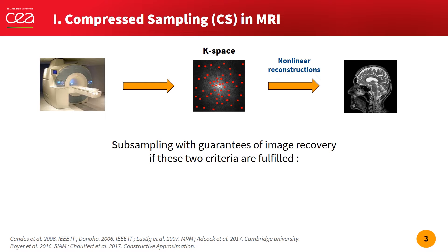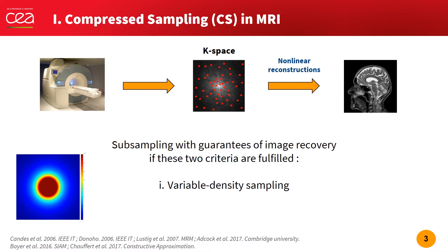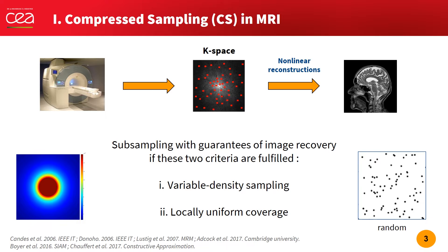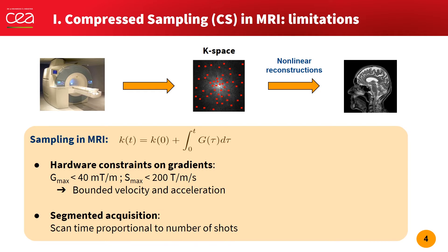It has been shown that the samples should be distributed along a variable density that is concentrated in the low frequencies of the k-space. Another more general principle for optimal sampling is to have a locally uniform coverage, which allows avoiding gaps and clusters of samples that are typical of random sampling. These two criteria are, however, difficult to respect in MRI, because samples are measured along very regular curves constrained by gradient amplitude and slew rate.